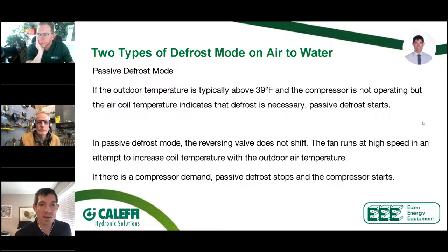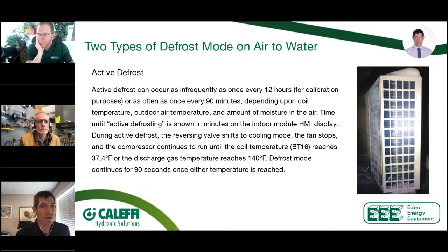the outdoor unit. On the next slide, the active, we're actually taking water that we have warmed in the buffer tank, and we're taking it back outside to heat it up a little bit. It's not going to be, you know, every second of the day below 37.4 degrees Fahrenheit outside or anything like that, but we are taking water that we've heated to go outside and make sure that that doesn't turn into a big ice box outside.